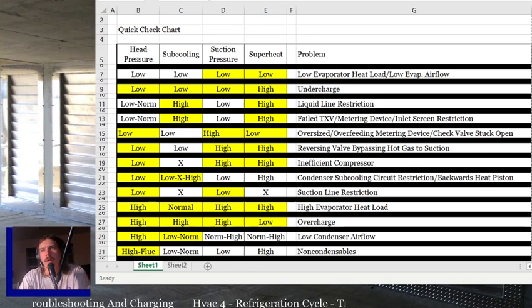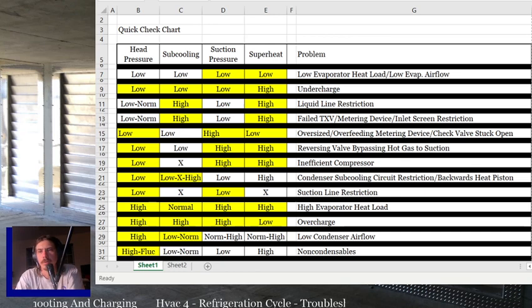Now, you need to know what outdoor temps and indoor temps are to determine whether or not these are low or high. So you still need indoor dry bulb, hopefully indoor wet bulb, outdoor dry bulb, return and supply on the indoor, condenser in and out on the outdoor. You still need those ambient temps, right? Because that's what tells you whether they're low, high, or normal. But other than that, as long as you know if head pressure is low or subcooling is low or suction pressure is low or superheat's low, that will usually be enough for you to determine most of the problems out there.